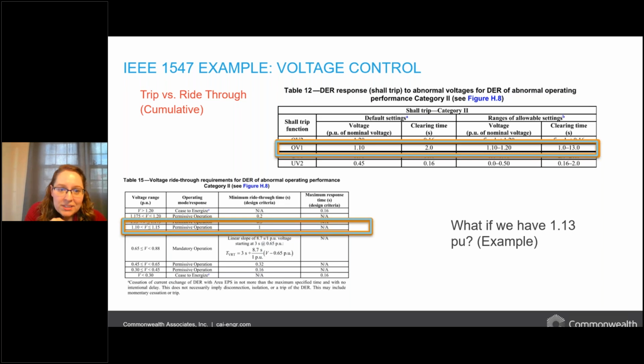And then in the lower left corner, we see with our trip chart that there is a range where there's a permissive operation. And if we're going to be riding through, the battery system has to be capable of riding through for at least 1 second. So this is really informing the battery system engineers on what the batteries could be asked to do when they are grid connected. And it also tells the operators what the allowable ranges are.